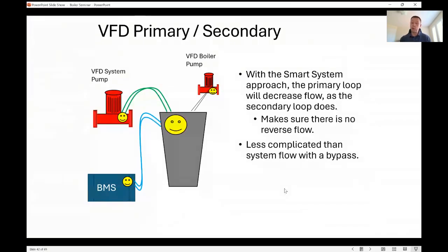Most boilers have that other ability too. If you want the BMS or the system to tell it what to do and how to do it, that's possible too. But I like it this way because boiler manufacturers spend a lot of time, effort and money to design algorithms for their controls so that they don't cycle and the boilers work properly. When you take that away, you're assuming whoever is controlling it is going to do a better job than the boiler manufacturer. Sometimes they do, sometimes they don't.